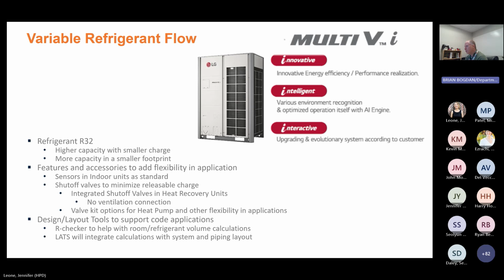Features and accessories: we're incorporating a lot of helpful features into the design. We're going to have sensors built into the indoor units as standard from our factory. We are going to offer shutoff valves to minimize the releasable charge. Those shutoff valves will come in two flavors. One would be just shutoff valve boxes that may come in single or 2, 3, 4 port options, similar to the heat recovery systems we sell today, but applying ways of using shutoff valves on heat pump systems.